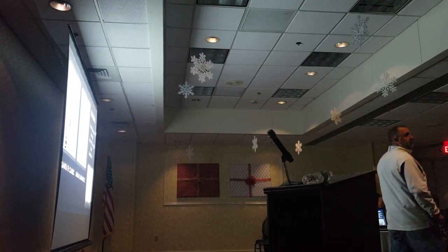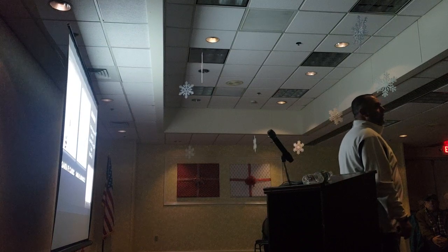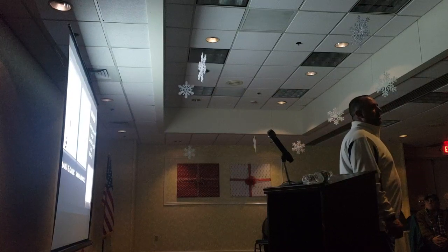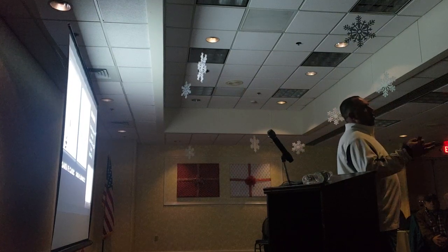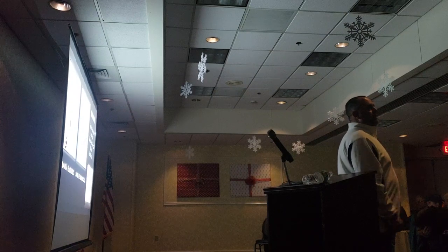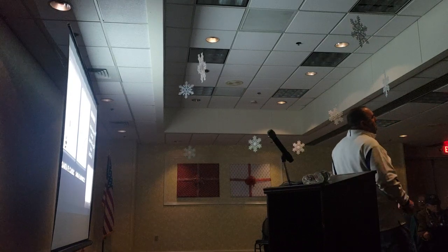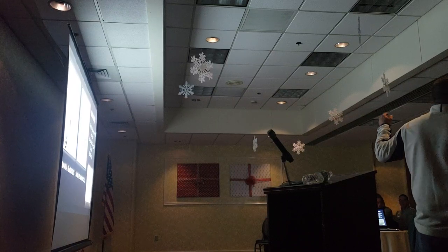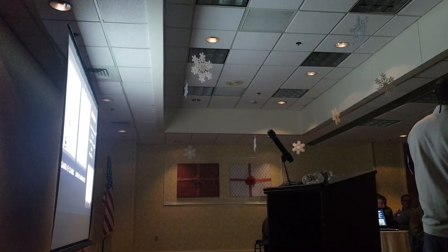How many square feet will the Advanced 2 do? About 2,500. They say 2,200, but on a wide open, I'll go 2,500. And the other one, the Compact, it's a little bit different machine, but on an open basement, I think 1,800 to 2,000 it calls for. So there's not a whole lot of difference on the water draw. The Compacts are nice, but the Advanced 2 for the money is not much more, and it's a much better machine. We do put the Compacts in, but they're small machines.